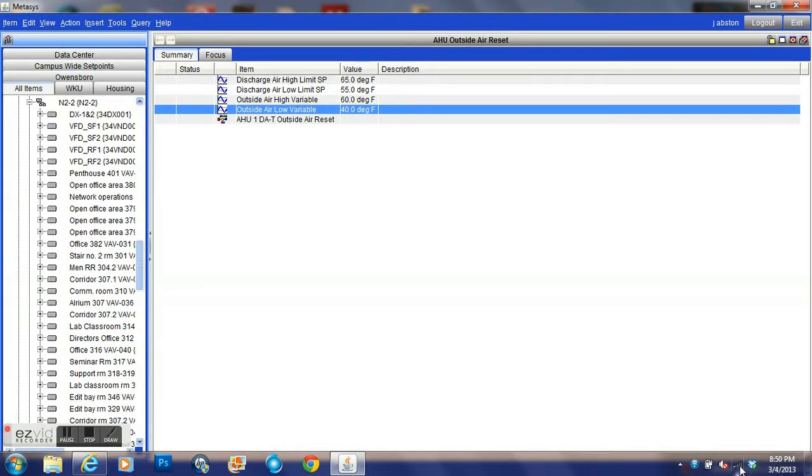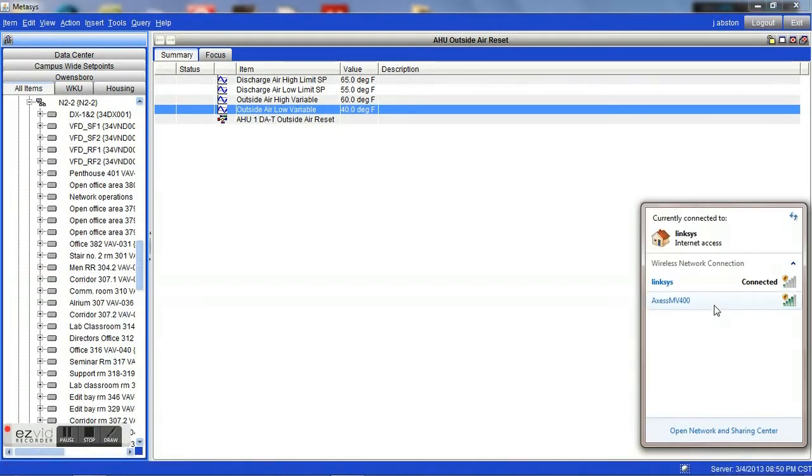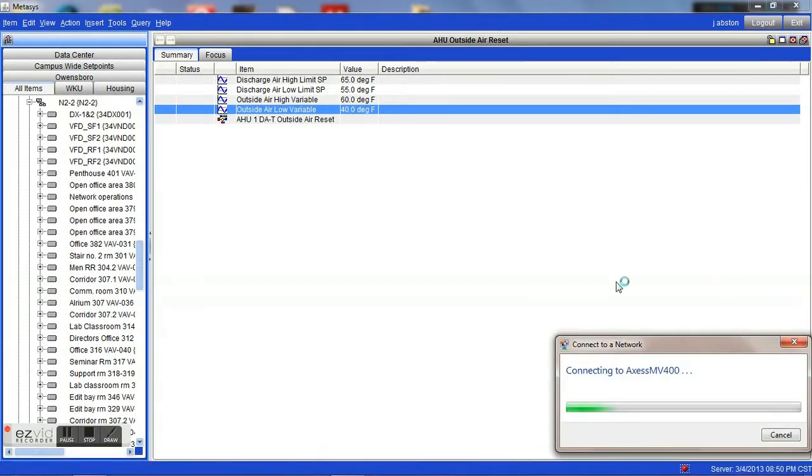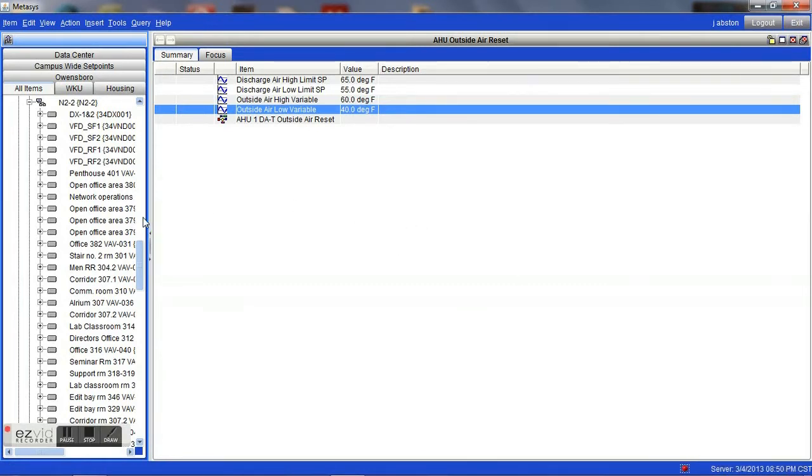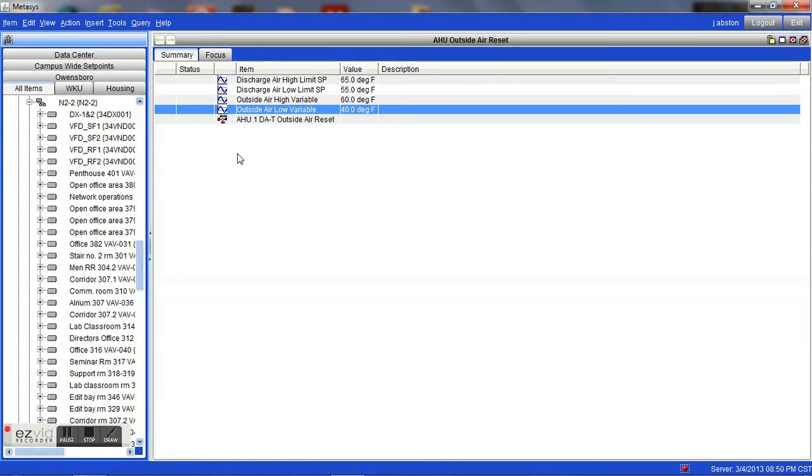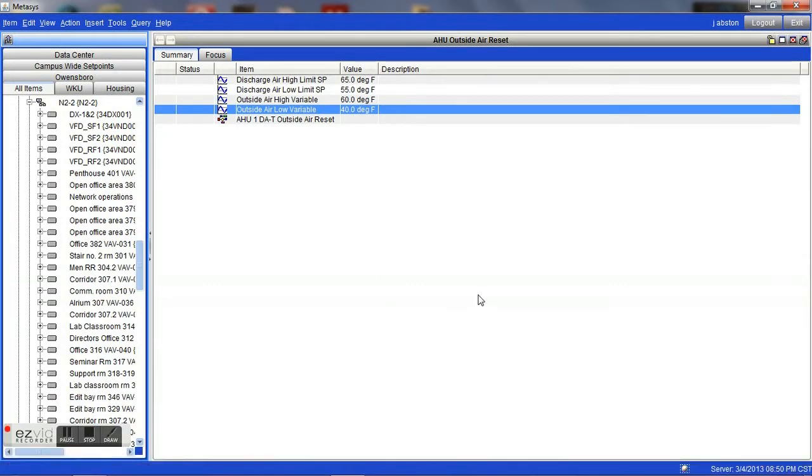Now, one of the things that we can do that will really help to improve the effectiveness of our air handling system is to raise the discharge temperature on the air handler. By raising the discharge temperature on the air handler slightly, we allow the hot water system to unload a bit. It does not necessarily need to work as hard to keep the spaces warm.